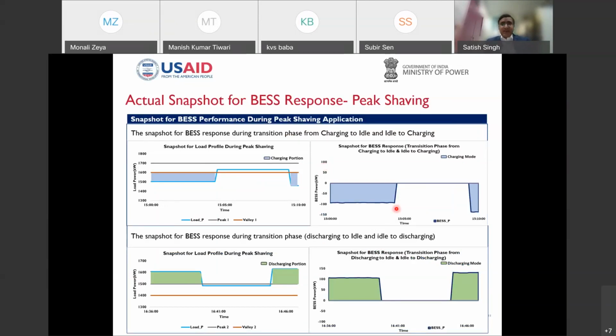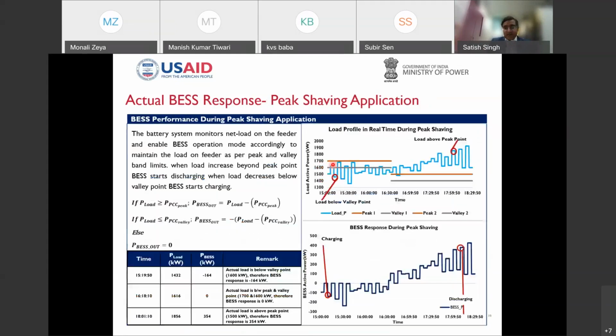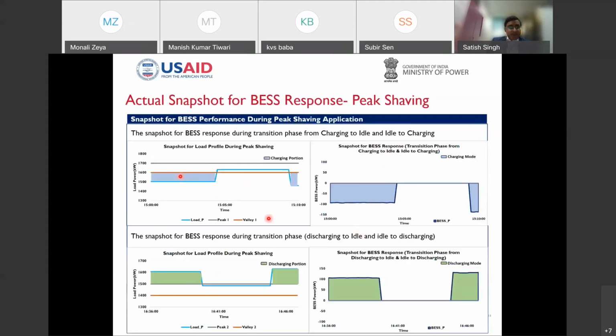If we want to implement that, we can use a battery to do it very effectively if there is a larger capacity size. Here again, we have just captured these snapshots in the next diagram. Here we are saying if 1500 and 1600 was my overall limit, how these load values would trigger the battery to charge or discharge in real time. If my load is beyond 1500, the battery is discharging, and again there is a toggle once this goes beyond the 1500 value, and again it is in discharging mode.